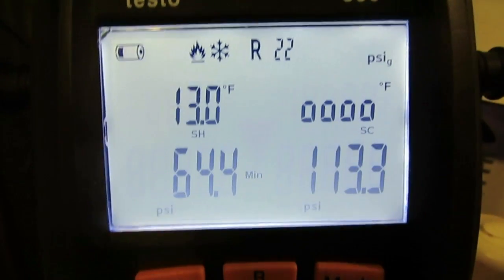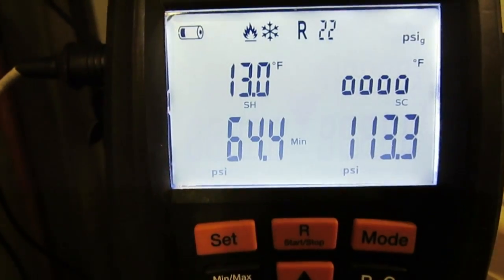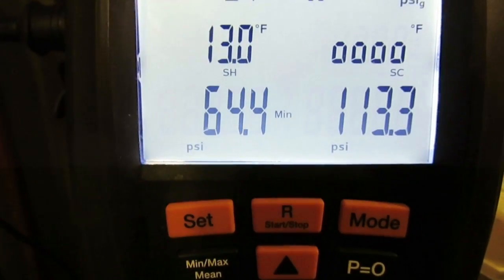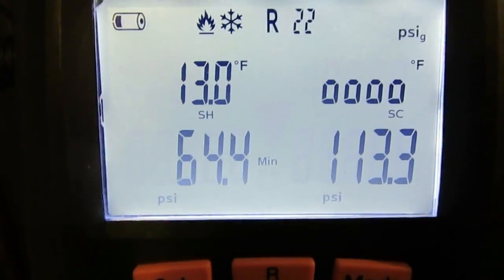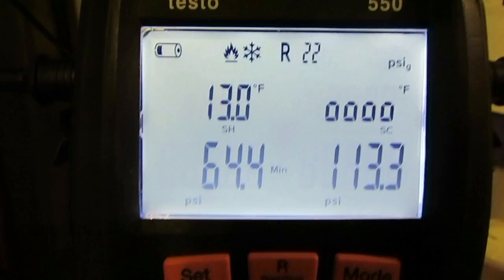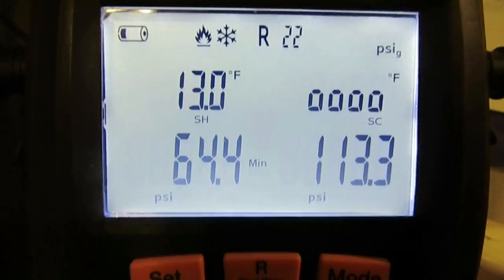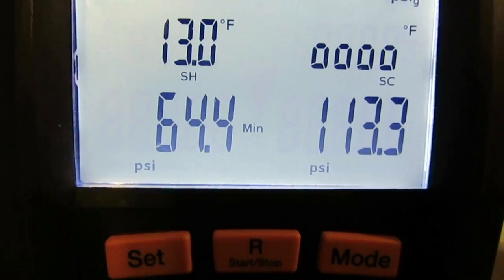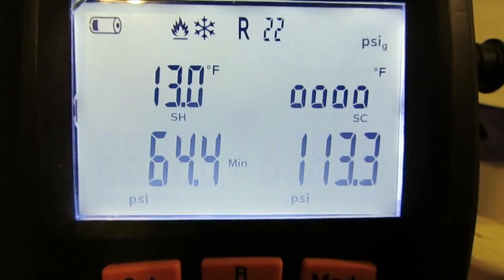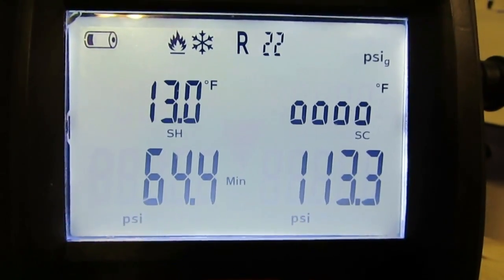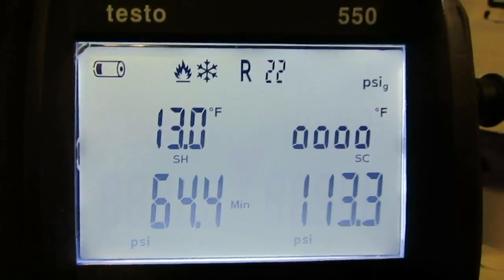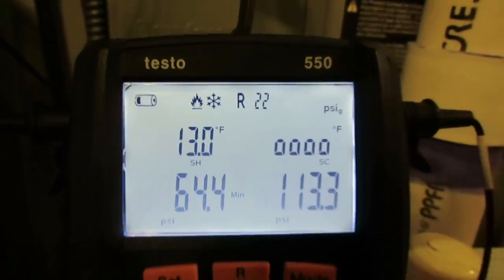It's 13. I wonder what that means. Actually I don't think it means anything bad whatsoever. Basically what I've been told by several of my friends and from a lot of the reading I do, I read all the PDFs I possibly can, and a lot of my buddies have told me that most of the manufacturers now, not all of them, but most of the manufacturers of the TXVs are setting them up, are designing them to be a 12 degree superheat.